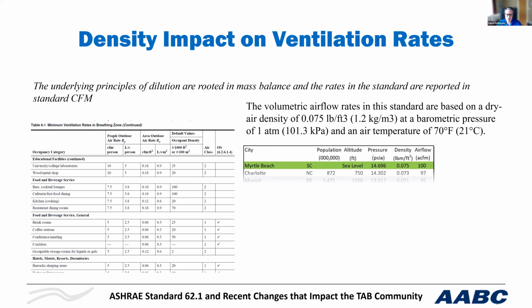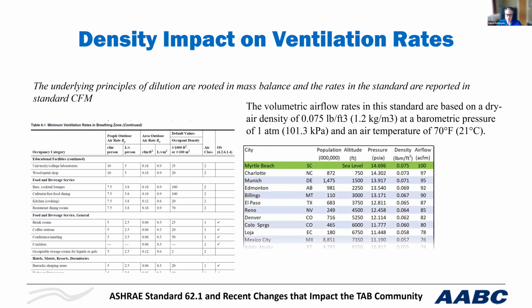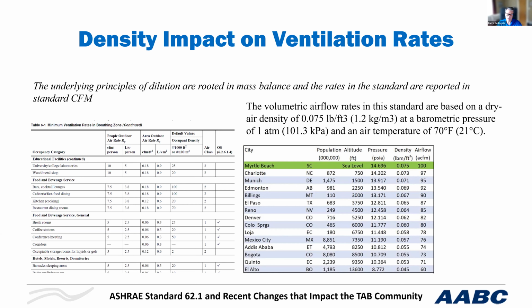So let's take a look, as the elevation increases, what is the impact? You can see, if we look at Charlotte, that's only 800 feet up. There's already a 3% deficit. And we're given plus or minus 10% in the balancing committee to balance it. You go to Colorado and Denver, and you're already 20% in the hole. Well, throw that 10% out the window, right? You're already not meeting 62.1. Another thing that affects density is temperature, as I listed there. The standard condition is 70 degrees that the ventilation rate procedure is listed to.